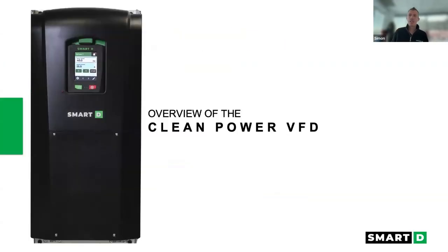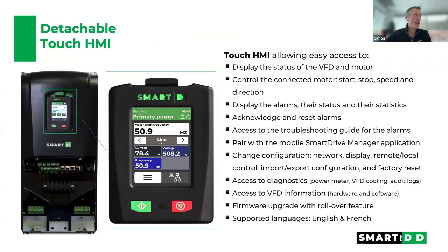So, last section of the presentation, I'll give you a quick view of what the drive looks like in practice. We have a touchscreen HMI. This enables us to do quick updates of the drive. So the drive can be fully updated through the USB port. You can kind of see it, it's there. In 5 minutes, you update the drive. If we add new features, new functions, the HMI gets updated. So you don't need to relearn buttons. It's very intuitive. If there's an alarm, you can read it in plain English.